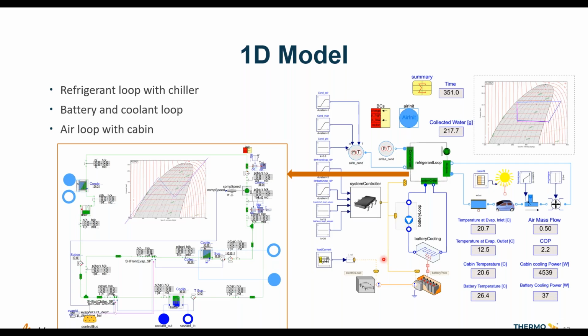And what you see on the left-hand side exploded is the refrigerant loop. This is a 1D model of the refrigerant system, including all of the components. In this case, we're doing a parallel loop, so it's a compressor followed by an air condenser, and then split paths. One path is for the front evaporator—that's where we get our cabin cooling. The second path is the battery chiller, where the cooling for the battery will come from.